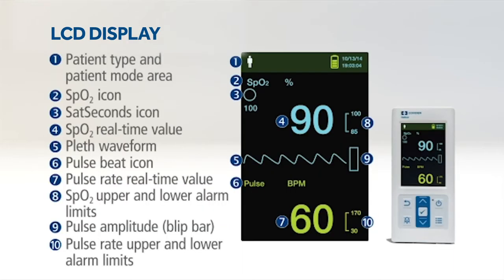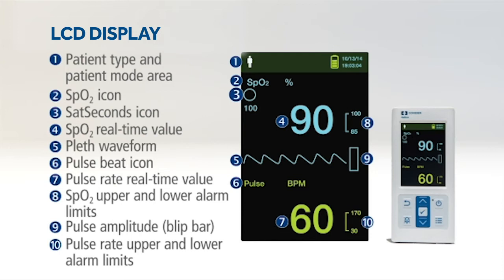The vivid 3-inch color LCD screen supports a robust data set, including real-time SPO2 and pulse rate values, Nellcor Sat Seconds alarm management, a pleth waveform, blip bar and tabular trend data.